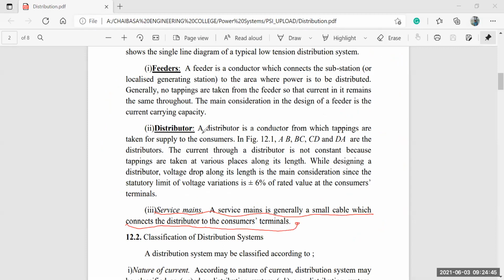Now a distributor is a conductor from which tappings are taken for supply to the consumer. There is a figure showing the current through a distributor is not constant because tappings are taken at various places along its length. So while designing a distributor, voltage drop along its length is the main consideration, since the statutory limit of voltage variation is plus minus 6% of the rated value at the consumer terminals. This means if I require a certain amount of voltage or power, there would be a variation, it may increase or reduce.